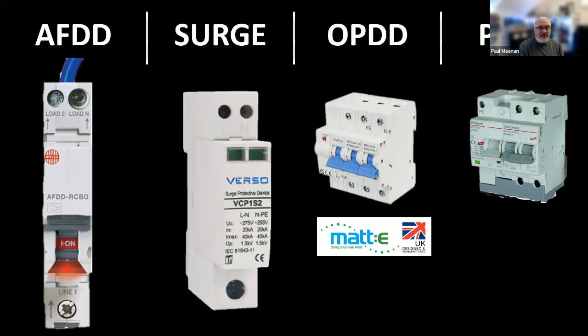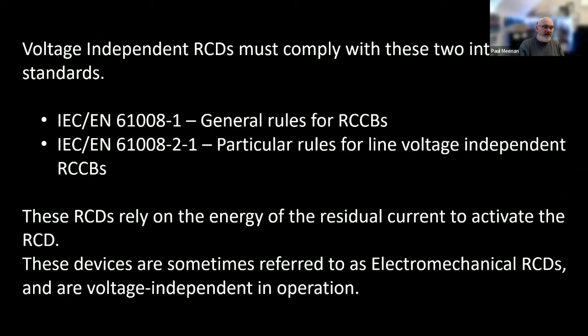If you look around the world, you've also got something called a OPDD. Similar to a surge device, but rather than looking for thousands of volts, it looks for voltages outside the normal bands. Say you've got 290 volts single phase to earth, it will look at that for a few seconds and then disconnect to protect your installation from any stresses or strains because of the network. So there's lots and lots of devices we now have to pick, and we have to configure them correctly, as well as our earthing.